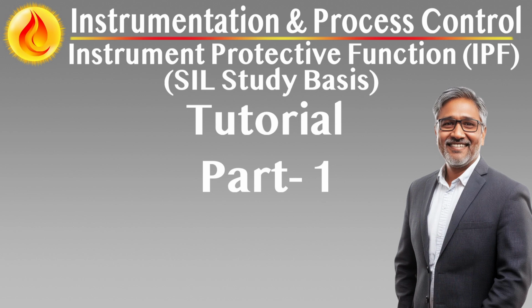Lifecycle documentation and validation. Each IPF must have a clearly documented life cycle, from initial hazard identification and SIL determination to design, installation, validation, and ongoing proof testing. The Safety Requirements Specification, SRS, defines the exact functional behavior, test intervals, and allowable degradation mechanisms. All maintenance and bypass actions must be logged and auditable, with compensatory measures defined to retain functional integrity during IPF outages.